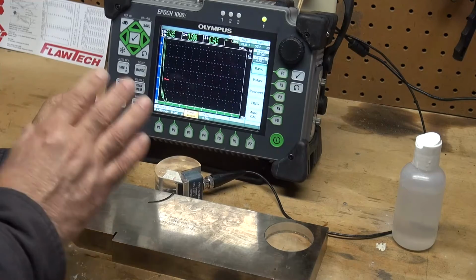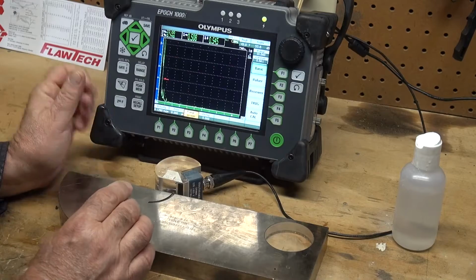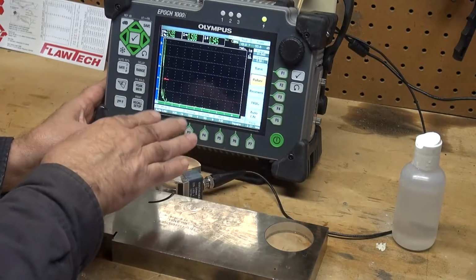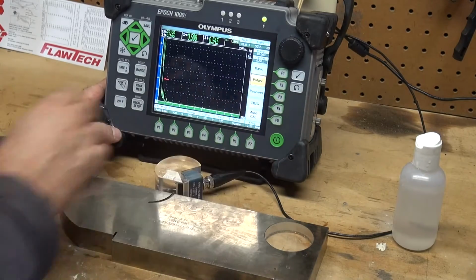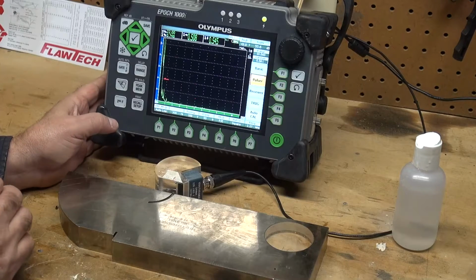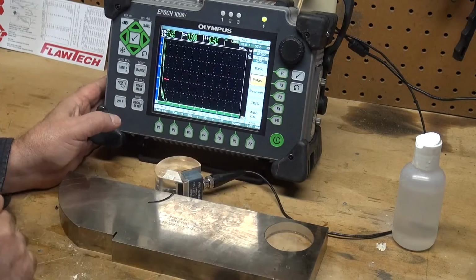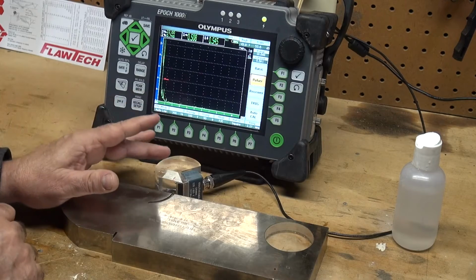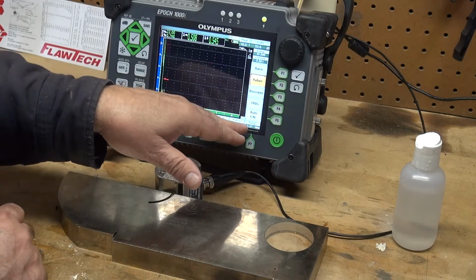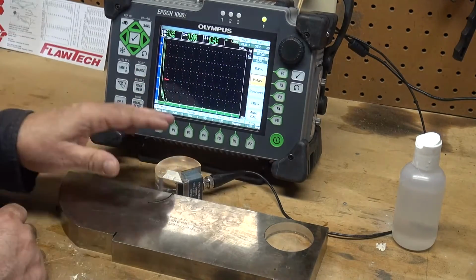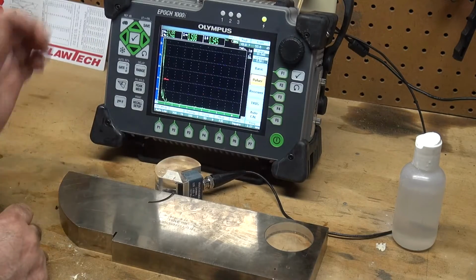And remember our receiver and our pulser. We want to make sure that we set our pulser at 2.25 megahertz. In the case of the Olympus, 2.27 megahertz. But we always want to make sure that our frequency set matches our transducer.